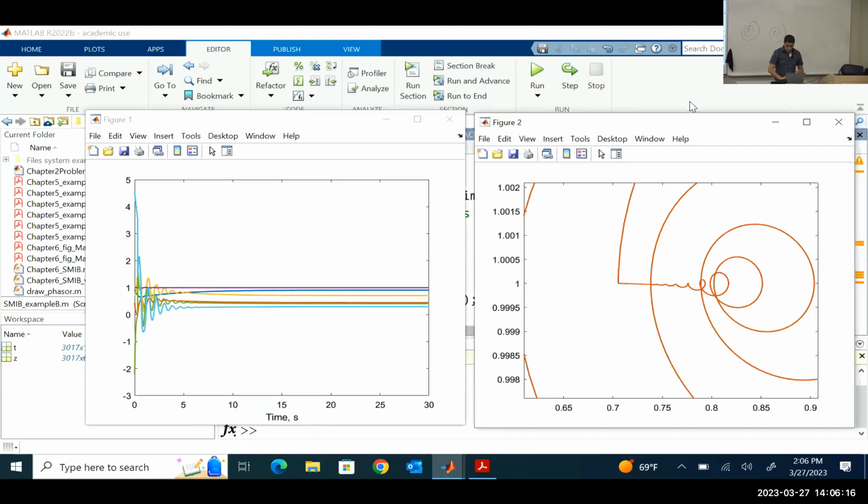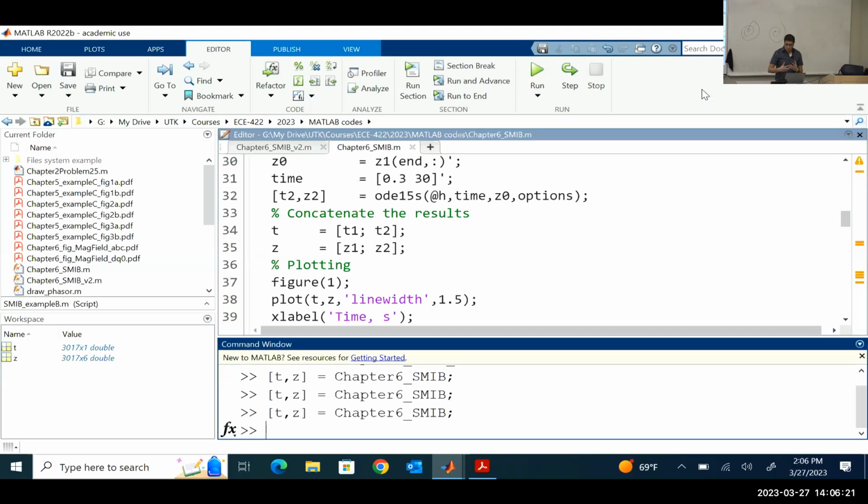We're going to tweak this. Why? Because we are engineers. For example, we need to specify the protection scheme in this system, and for the protection scheme, we need a breaker. We need some relays and measurements that can send a signal to this breaker to open the contacts if needed. But there are different technologies, different types of breakers that are faster or slower, and we need to make sure that whatever breaker we have operates at a good time. What is a good time? When the machine is still stable. We're going to have rotor angle stability. So for that reason, it's very important for us to study the critical clearing time, because we need that for the specification of our protection scheme.